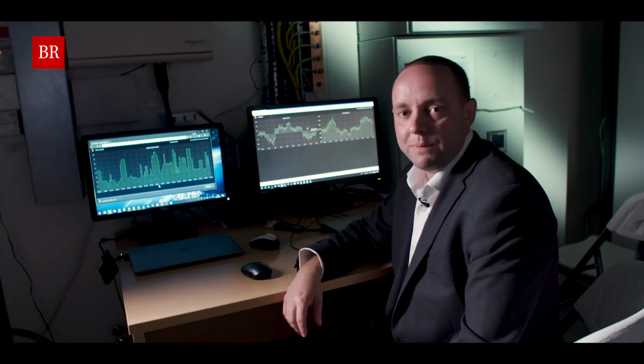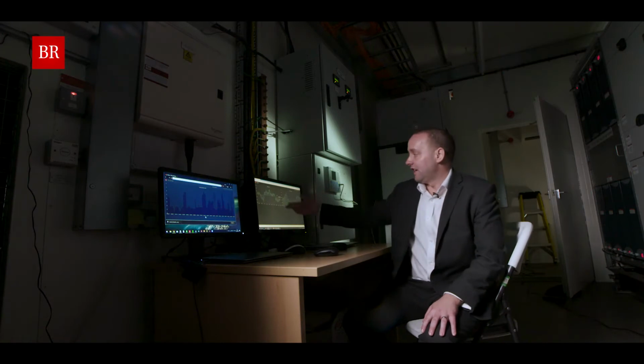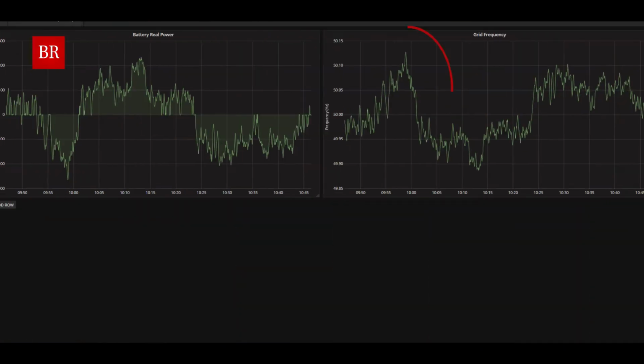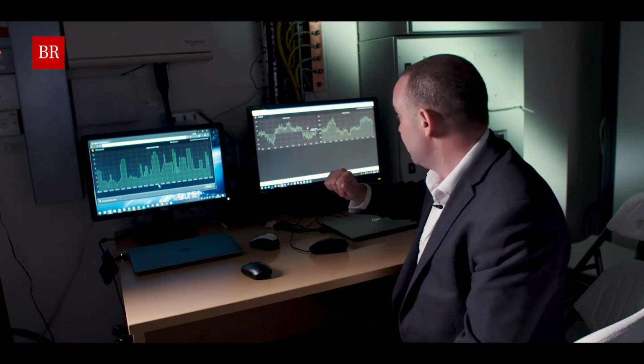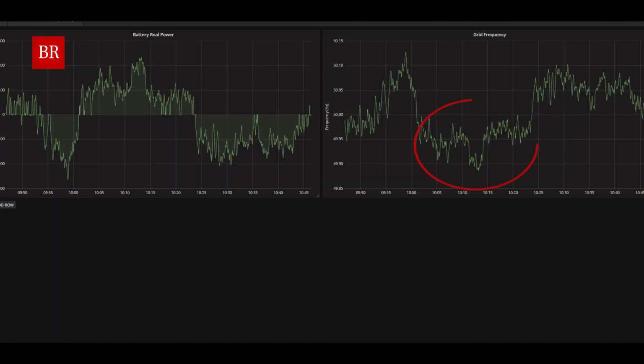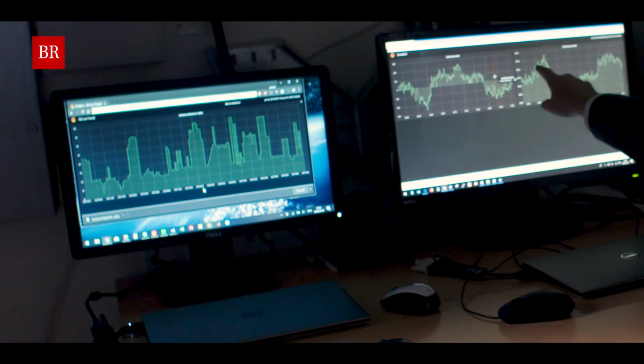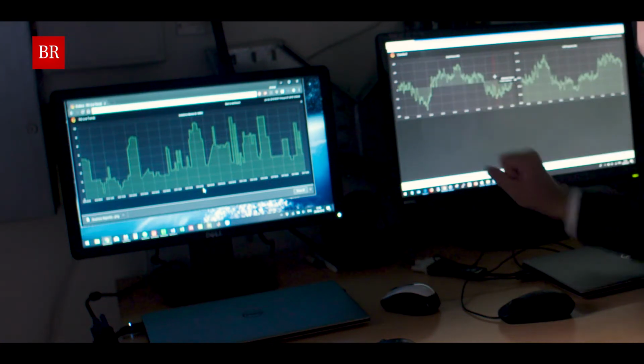I'm going to show you how the battery operates. On the screen here, I have two charts. There's a big increase in frequency here, which means there's too much power on the grid. Our battery now takes that power off the grid to rebalance those two, demand and supply. The frequency drops down below 50 hertz, and you can see our battery responds again, providing power to the grid to keep it in balance. As soon as this frequency changes, the battery reacts straight away.